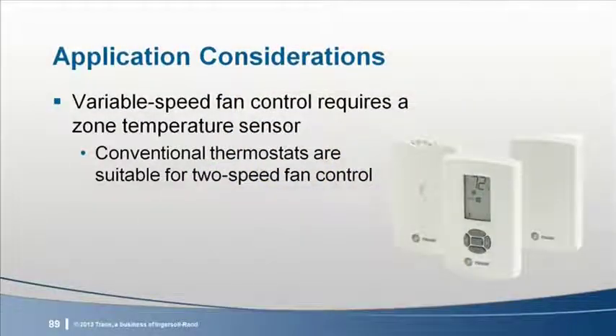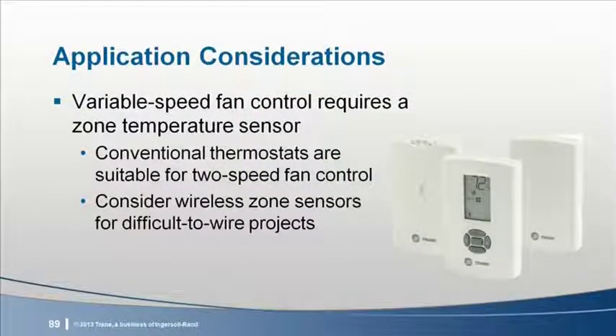The final consideration we'll discuss is that a system with variable speed fan control will require a zone temperature sensor rather than a thermostat. John mentioned earlier that a conventional thermostat with Cool 1, Cool 2 control can be used for two-speed fan control, but not for variable speed control. For a new system, this is probably just something you want to be aware of when specifying or purchasing. But it can create a challenge if you're replacing an older piece of equipment with a new variable speed fan unit. If that old unit was controlled by a conventional thermostat, it will likely need to be replaced with a zone sensor. Thankfully, wireless sensing technology makes this a whole lot easier, especially for those projects where pulling wires would be difficult.